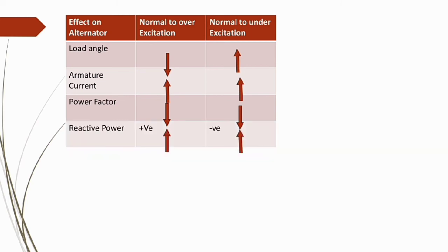Reactive power increases in both cases. In normal to over excitation, positive reactive power will increase, meaning more reactive power is supplied. In normal to under excitation, more reactive power will be absorbed. In both cases the reactive power will increase.